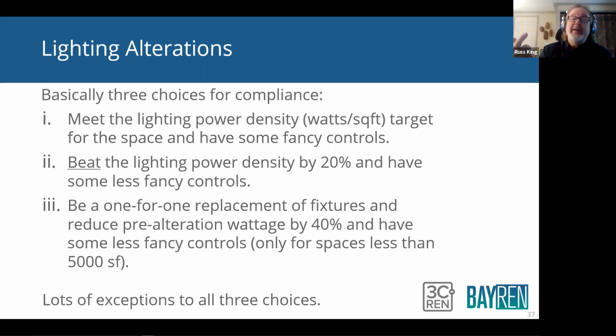The industry has decided that there's a reasonable amount of lighting for that type of occupancy. You go to a table, you look up that table, you look up that occupancy, and it'll say the recommended lighting power density for that space is X watts per square foot. You multiply it times the square footage of that space and you get your allowed watts, okay? So think of that as kind of the magic numbers. The lighting power density for that space is your target, all right? So if you're replacing more than 10% of your fixtures, as long as when you're done and you have these controls, the wattage is less than your lighting power density, you're done. That's all you have to do, okay?